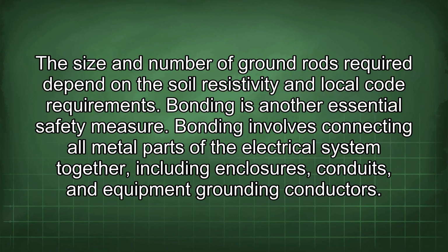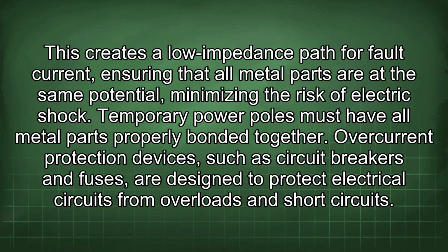Bonding is another essential safety measure. Bonding involves connecting all metal parts of the electrical system together, including enclosures, conduits, and equipment grounding conductors. This creates a low impedance path for fault current, ensuring that all metal parts are at the same potential, minimizing the risk of electric shock. Temporary power poles must have all metal parts properly bonded together.